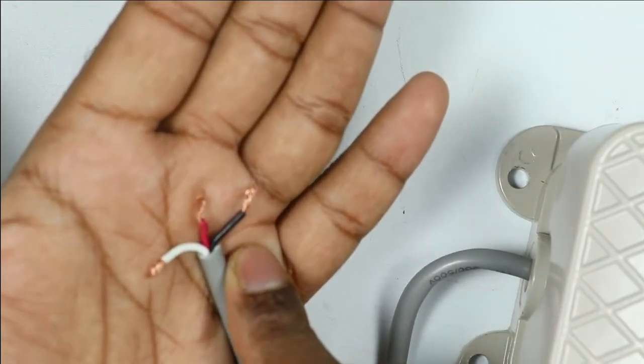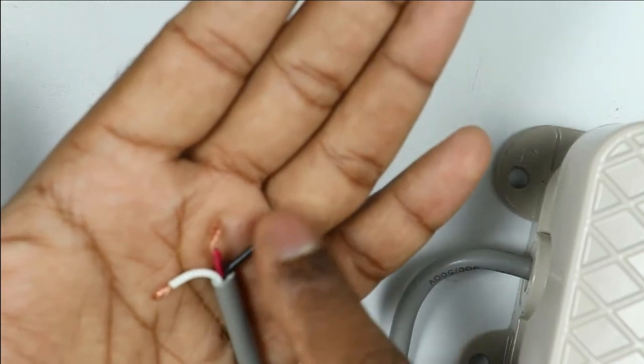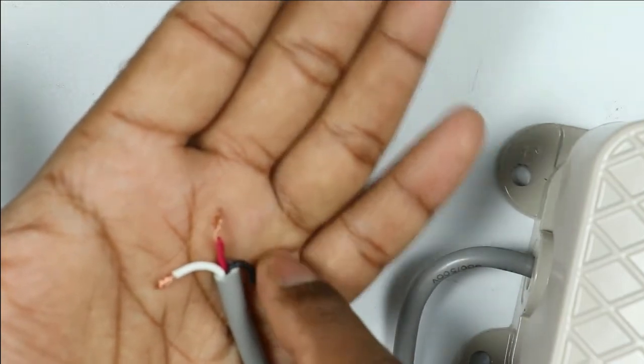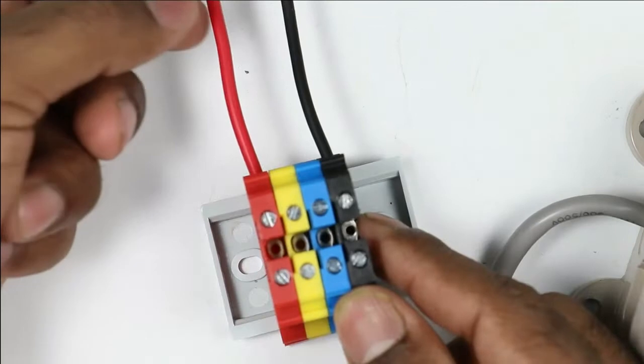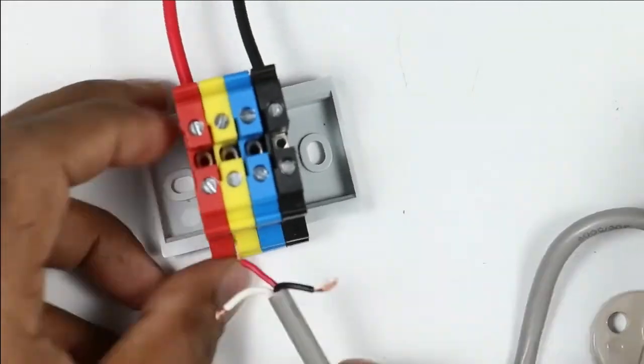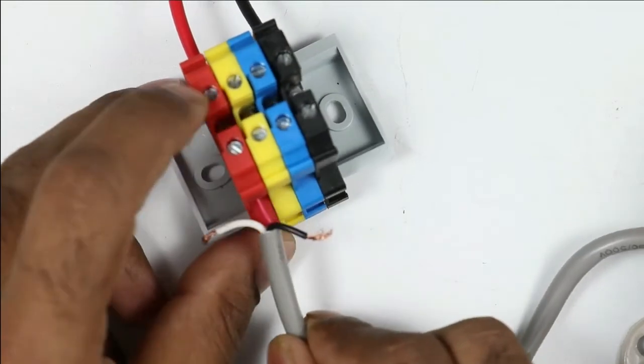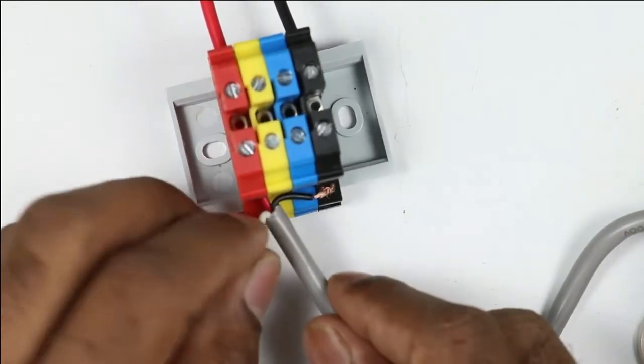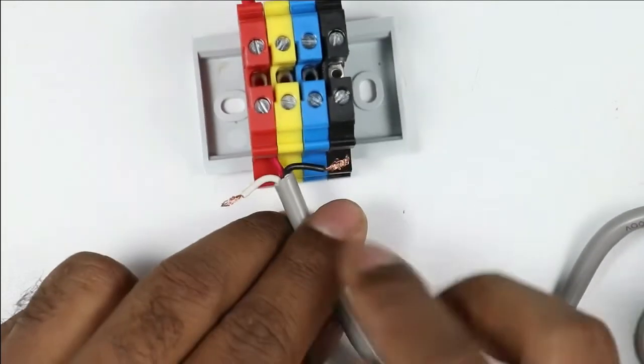We have to use the NO contact for connection. This means we will use white wire and red wire for connection. I am taking this red wire and the wire which is for phase supply. This wire is for incoming phase supply. I am connecting this red wire with the phase supply wire. From this white wire, we receive the output signal.